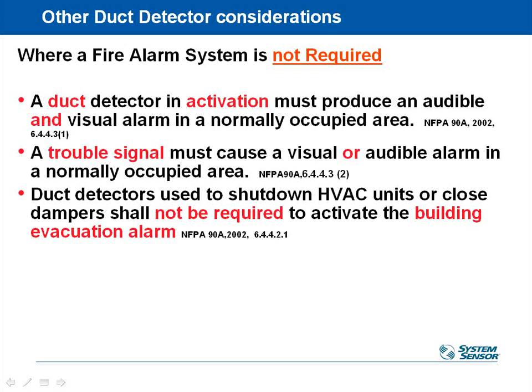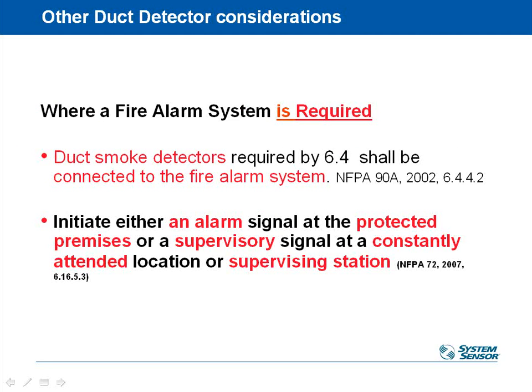Duct detectors used to shut down HVAC units or shut down smoke dampers shall not be required to activate the building evacuation system. So it doesn't have to necessarily tie into that system. Unless you have a fire alarm system that is required. So if you have to have a fire alarm system because of code, if it's requiring you to do it in NFPA, then you have to have the duct smoke detectors wired to that system.